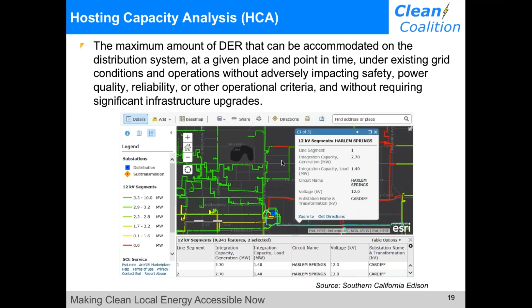This image details the type of information that a hosting capacity analysis uncovers. It's from a small section of Southern California Edison's distribution system, with details on a specific line segment of its grid and its ability to handle both new local generation from sources like rooftop solar, as well as additional load. For this particular line segment, which is 12 kilovolts and located within the Harlem Springs circuit of the Cardiff substation, it's projected that it can handle an additional 2.7 megawatts of additional generation and 1.4 megawatts of new load.